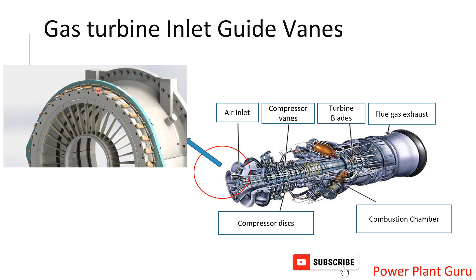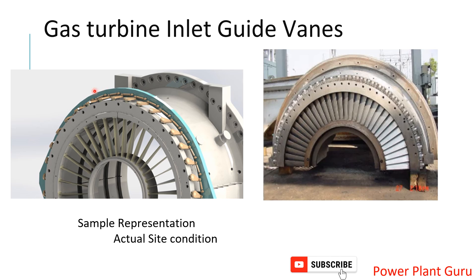Here we can see the IGV vanes and the mechanism which turns these individual vanes. Right now the path is fully open. If we turn all these small levers down, the blade will turn and try to close this path. At the minimum position, it will not be fully closed — there will still be some minimum amount of air flowing through.